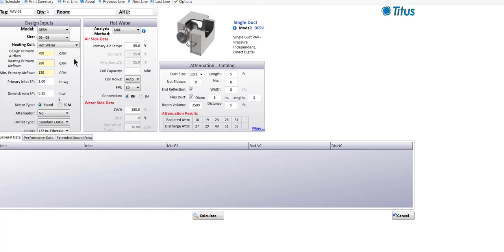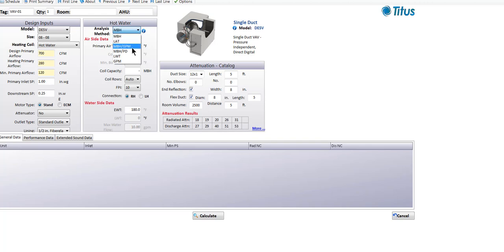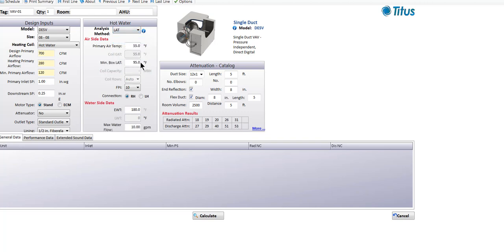If we go ahead and select the coil, we've got different analysis methods: we can select based on MBH delivered, leaving air temperature, a combination of MBH and GPM of water flow, MBH and water pressure drop, or leaving water temperature or GPM. I typically go with the leaving air temperature, and we need to be very careful there. I see a lot of situations where people have excessive leaving air temperatures, and that can easily lead to comfort issues in the space.